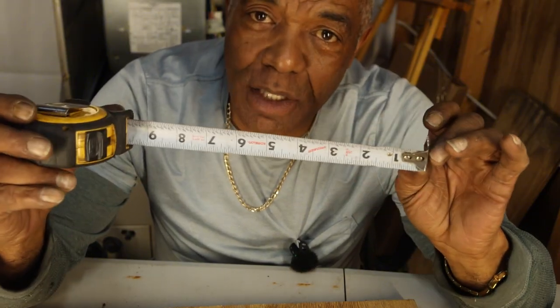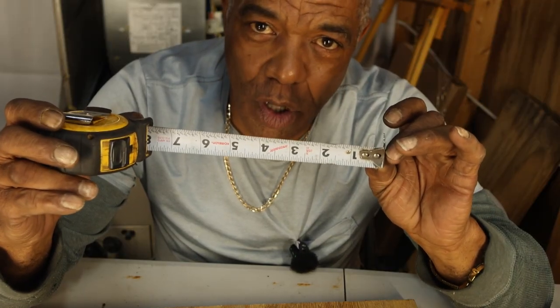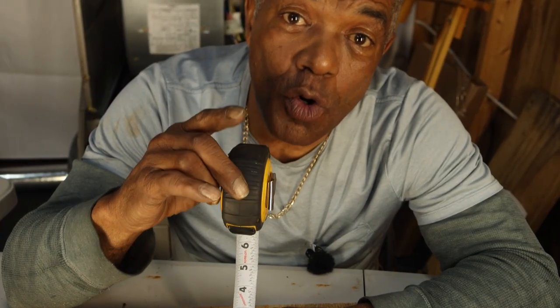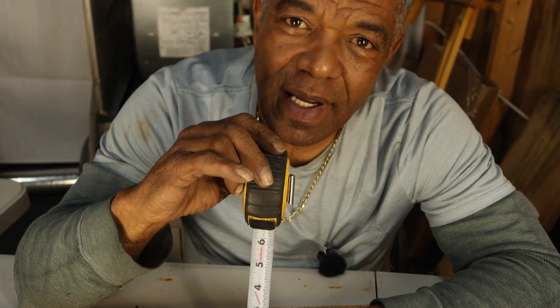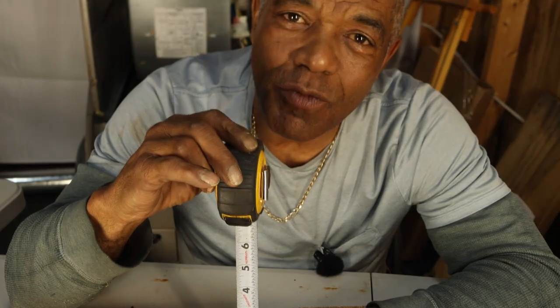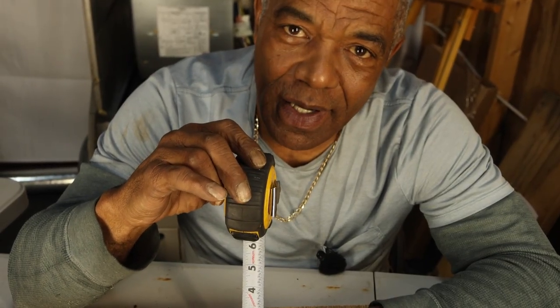Normally, I take the measurement of the existing coil, its width, its length, and its height. And then I call different vendors and I find one that has a coil with those same dimensions. Then I don't have to alter the ductwork. I can take the existing coil out, put the new coil back and tie it right back into the exact duct that's there. Same thing with gas furnaces, same thing with air conditioners. I have accounts and relationships with almost every HVAC manufacturing company in this region.